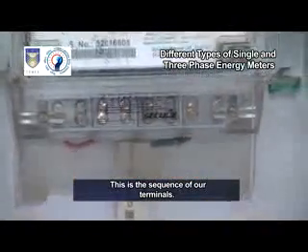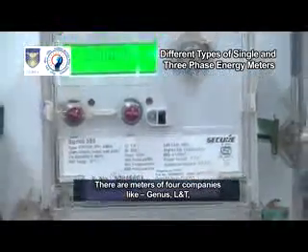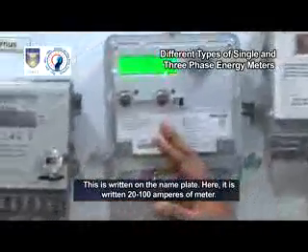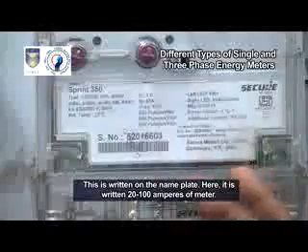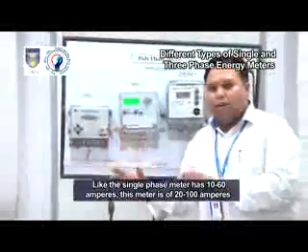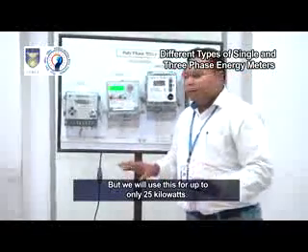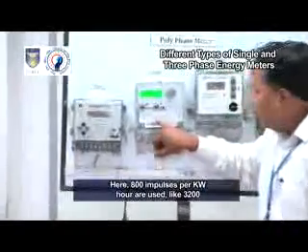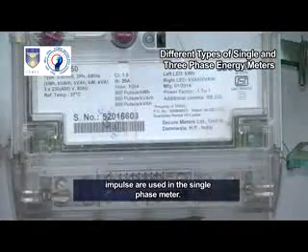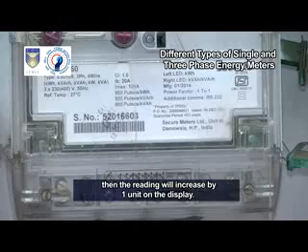Speaking about the nameplate, this meter is from the Secure company. Meters are available from four companies: Genus, L&T, Secure, and Landis and Gyr. The current range is 20 to 100 amperes, compared to 10 to 60 amperes for the single-phase meter. This Secure meter can be used up to 40 kilowatts, though it is used up to 25 kilowatts here. It uses 800 impulses per kilowatt-hour, whereas the single-phase meter uses 3200 impulses. When 800 impulses are completed, the reading increases by one unit on the display.